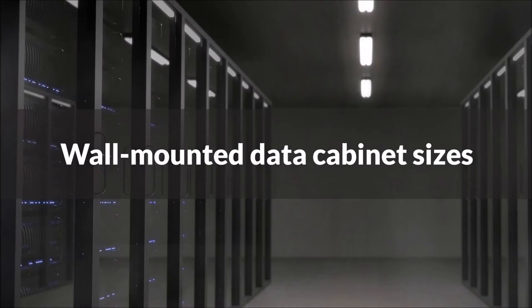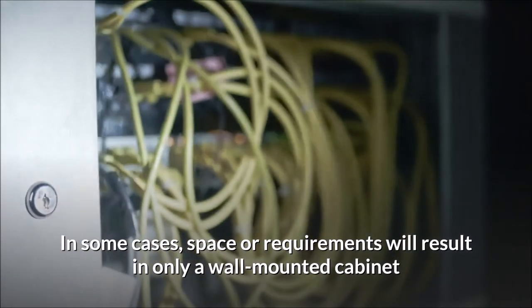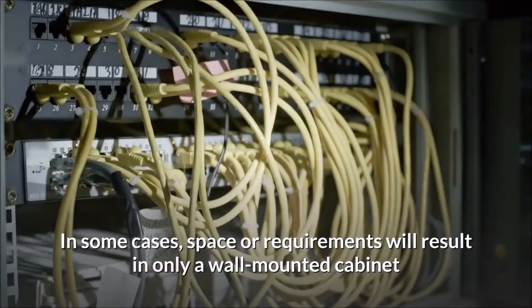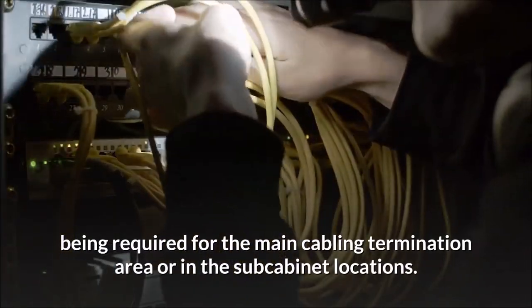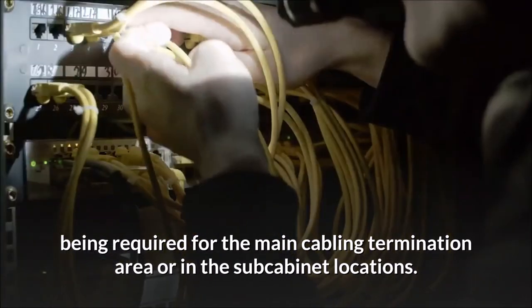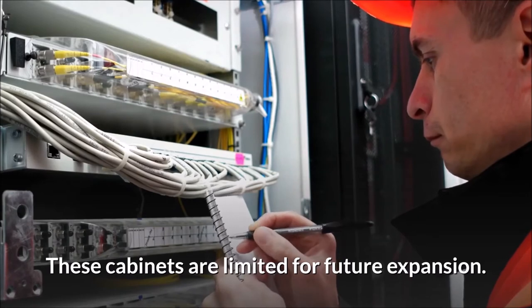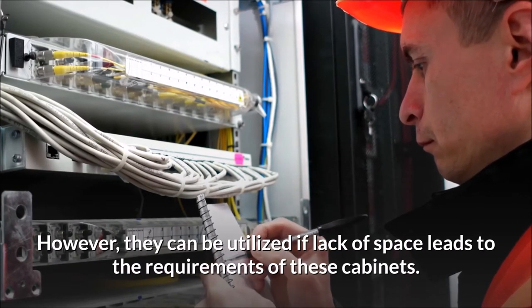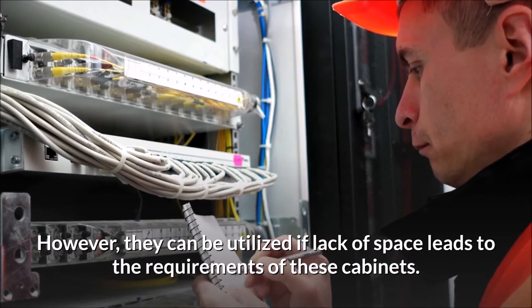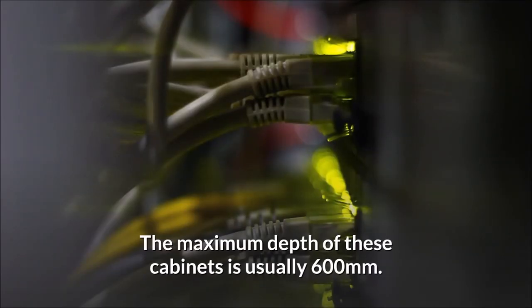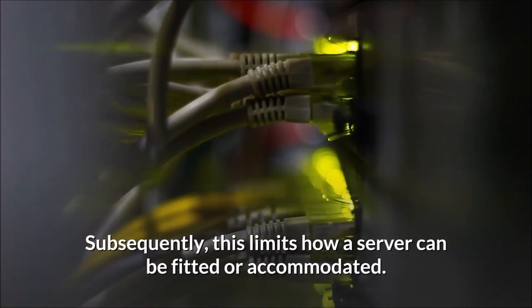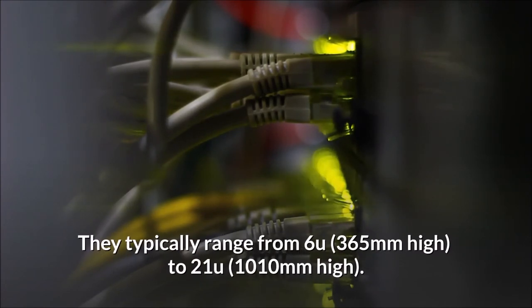Wall-mounted data cabinet sizes. In some cases, space or requirements will result in only a wall-mounted cabinet being required for the main cabling termination area or in the sub-cabinet locations. These cabinets are limited for future expansion. However, they can be utilized if lack of space leads to the requirements of these cabinets. The maximum depth of these cabinets is usually 600 mm. Subsequently, this limits how a server can be fitted or accommodated. They typically range from 6U, 365 mm high, to 21U, 1010 mm high.